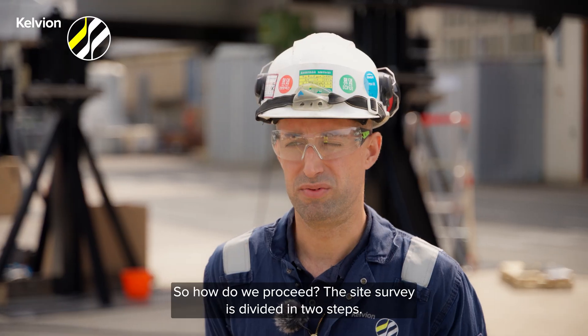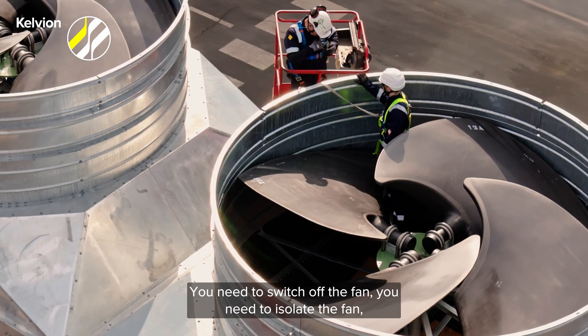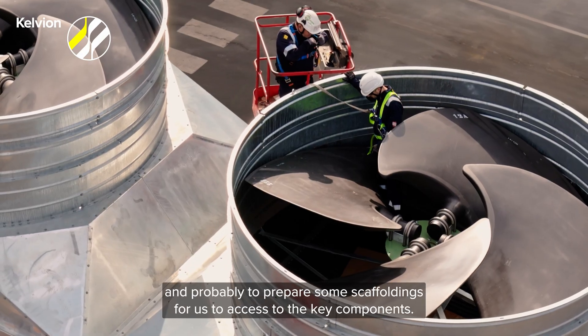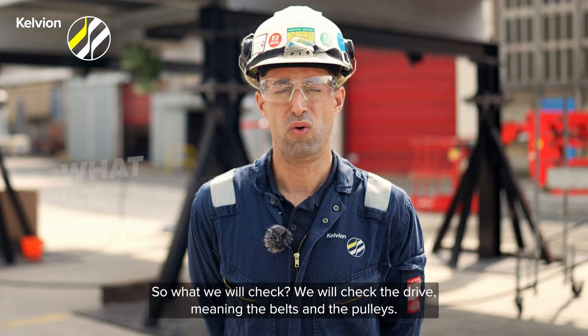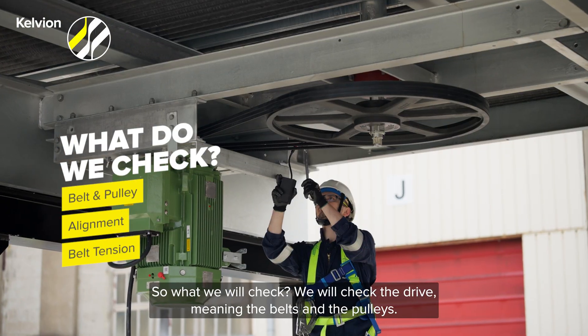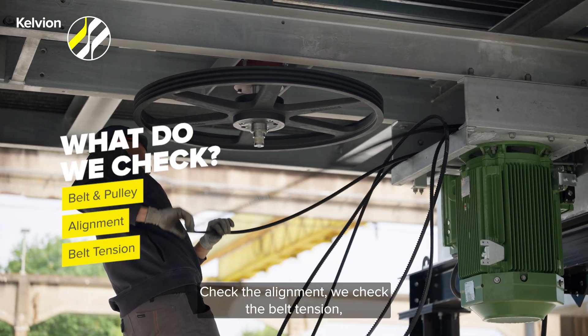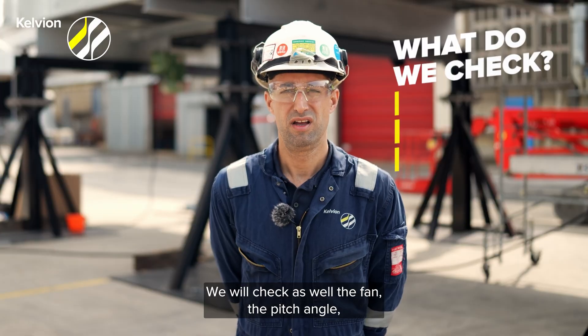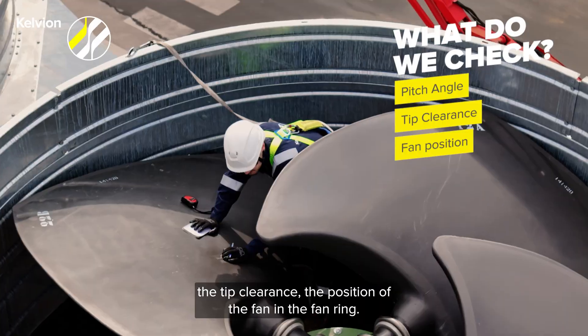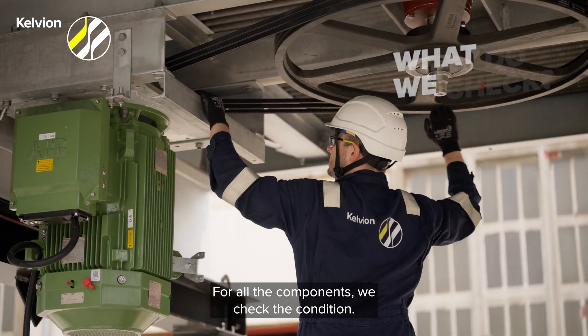The site survey is divided in two steps. Step number one is the mechanical inspection. You need to switch off the fan, isolate the fan, and probably prepare some scaffolding for us to access the key components. We will check the drive — meaning the belts and the pulleys — check the alignment, the belt tension, the belt condition and pulleys condition. We will also check the fan: the pitch angle, the tip clearance, and the position of the fan in the fan ring.